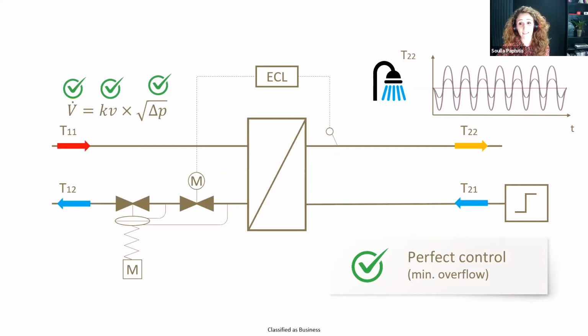But there are still cases, however, where this is not possible. For instance, where you're looking at oversized valves or uncommissioned controllers. However, in those cases, the results with the motorized control valve will still be better than having no control on there at all. So in most recent years, we've looked at using PICV controls, which basically combine the motorized control valve and the differential pressure controller into one complete unit.